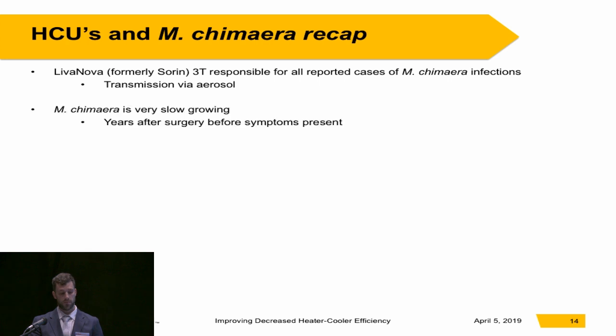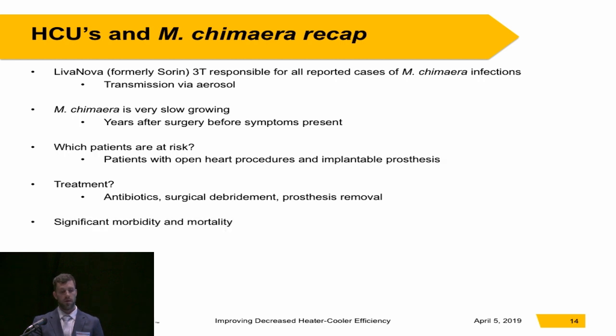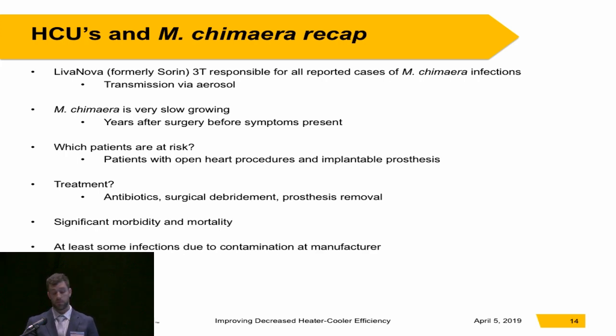The treatment — there is no real gold standard at this point. We try antibiotics, surgical debridement, and then prosthesis removal. It's associated with significant morbidity and mortality. At least some of these infections were due to contamination at the manufacturer, and it still likely remains some type of infection risk. Kuhl and colleagues looked at the design of the LivaNova 3T and found a design flaw unique to the 3T that allows bacteria to aerosolize and release into the operating room. The FDA is also aware of some 3T devices manufactured after the September 2014 protocol change that have tested positive for M. chimaera.